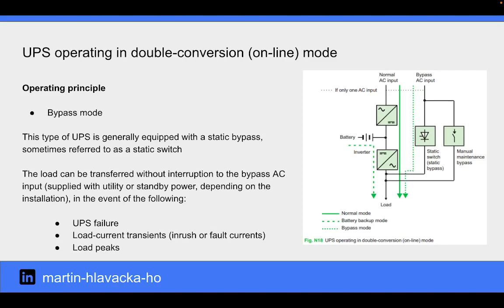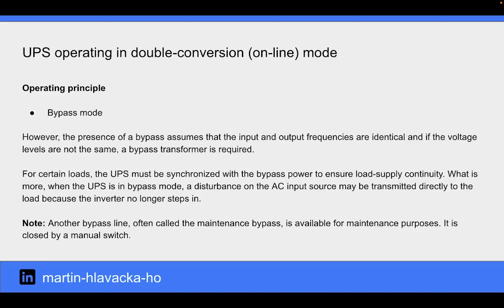In bypass mode, the load can be transferred without interruption to the bypass AC input in the event of UPS failure, load current transients, or load peaks. However, the presence of a bypass assumes that the input and output frequencies are identical, and if the voltage levels are not the same, a bypass transformer is required. For certain loads, the UPS must be synchronized with the bypass power to ensure load supply continuity. Furthermore, when the UPS is in bypass mode, a disturbance on the AC input source may be transmitted directly to the load because the inverter no longer steps in.